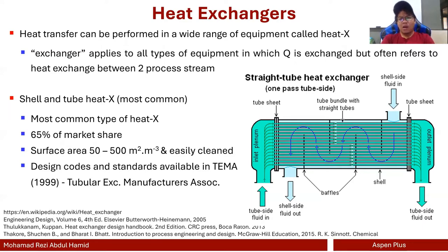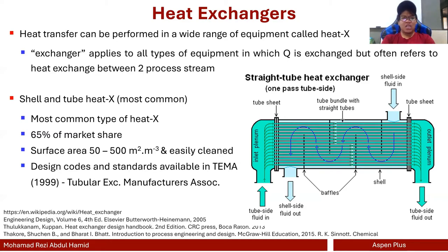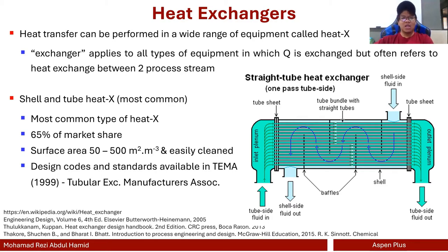There are different types of heat exchangers — plate and frame, flat — but shell and tube is probably the most common one. In this case, we're going to focus on the shell and tube heat exchanger only. They are the most common heat exchangers, occupying around 65% of the market share. The tubes are not too large and not too small — you can pack around 50 up to 500 square meters of surface area, and one advantage is that they can be easily cleaned.